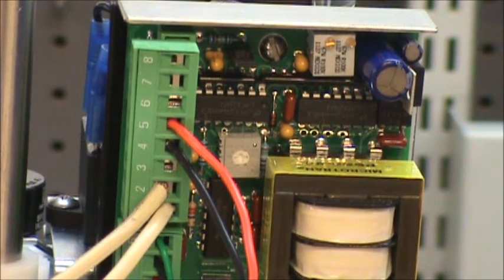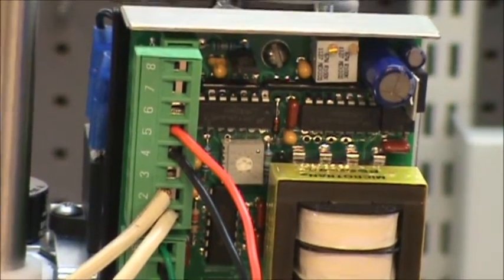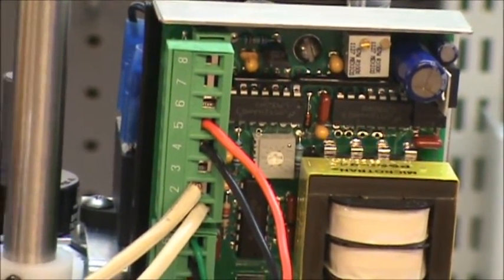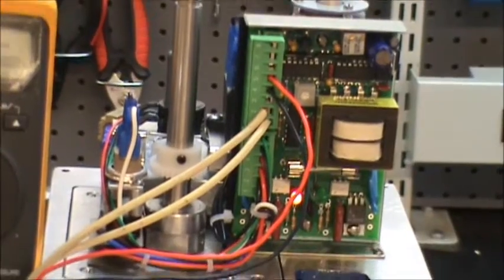The span controls the open, so you're going to give it a 20 milliamp signal. And you notice the red LED light down here is on. That light will stay on as long as it's traveling.